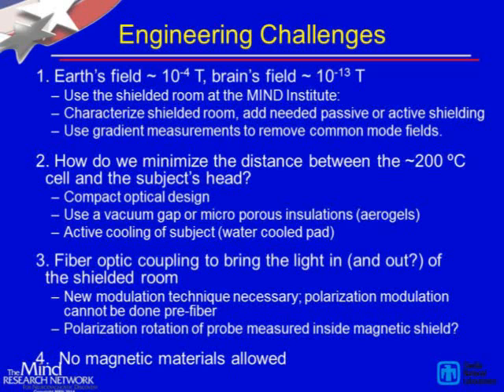As I mentioned earlier, we wanted to use fiber optics to bring light in and out of the sensor. So we're looking at some modulation techniques that allow us to use the fiber optics and things like that. Also, in developing the magnetic sensor, we can't allow any magnetic materials inside the sensor. That's always an engineering challenge when you can't use any metal components, or you've got to minimize the metal components.